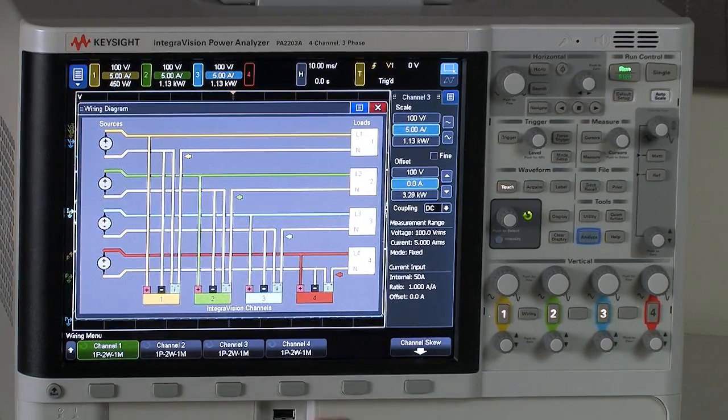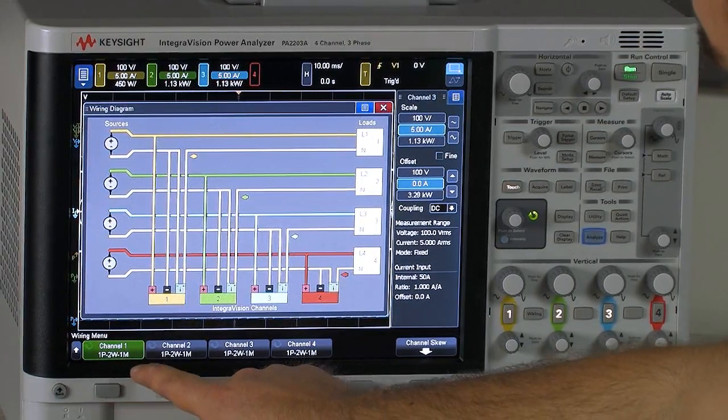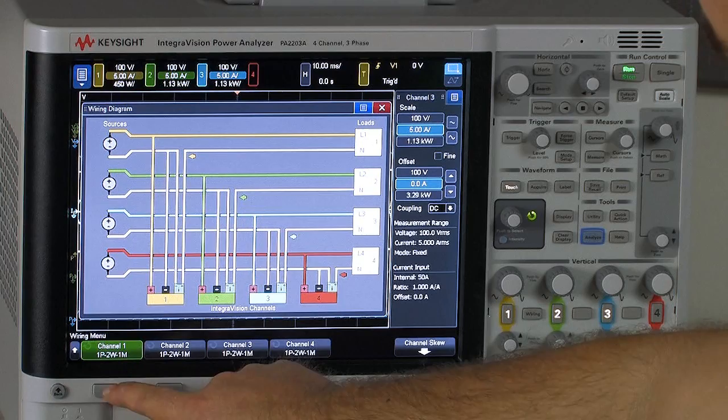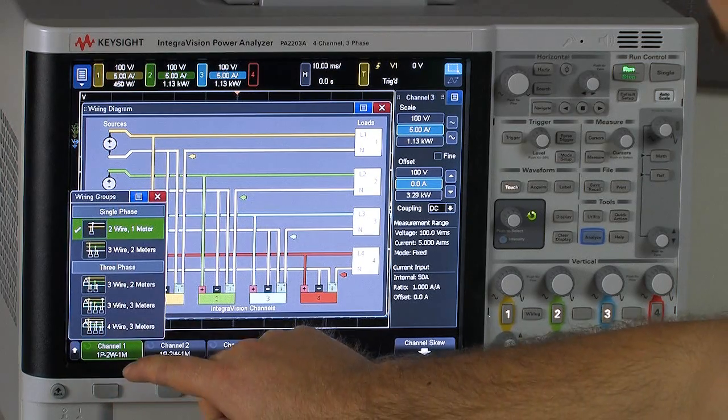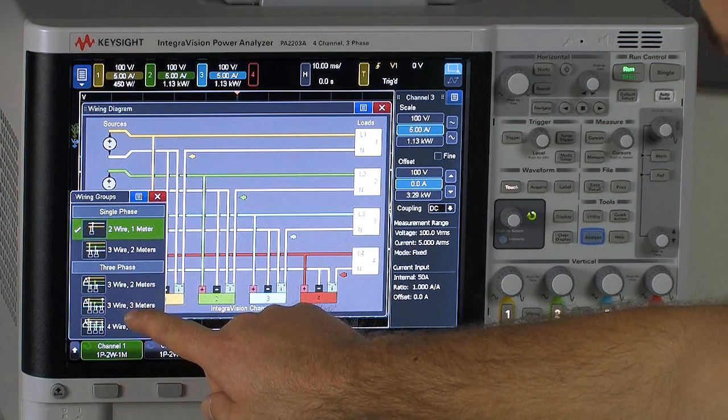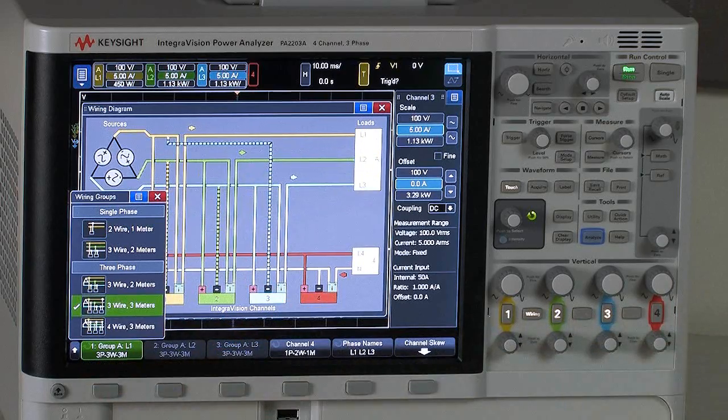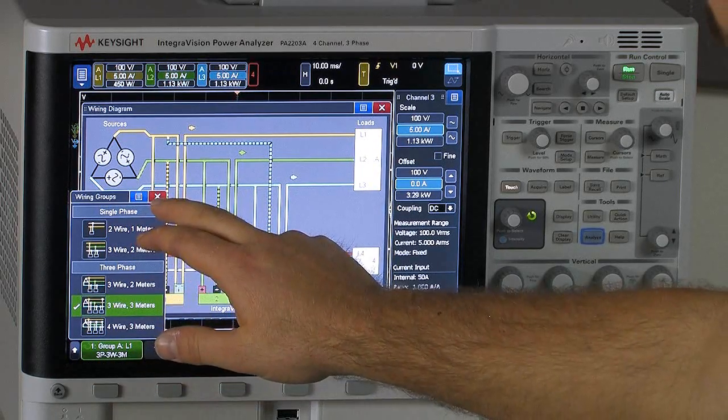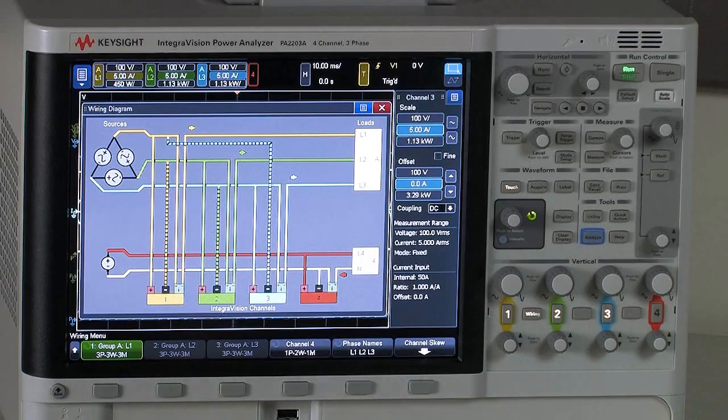So to start out, to group them, I'm just going to go right down here to the channel selection key, and we're going to start off with a three-wire, three-meter, three-phase configuration that you would typically use for measuring in a delta configuration.